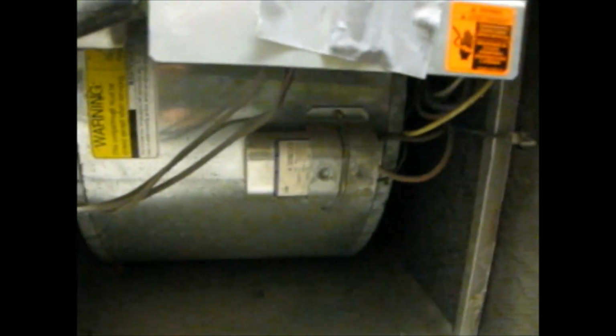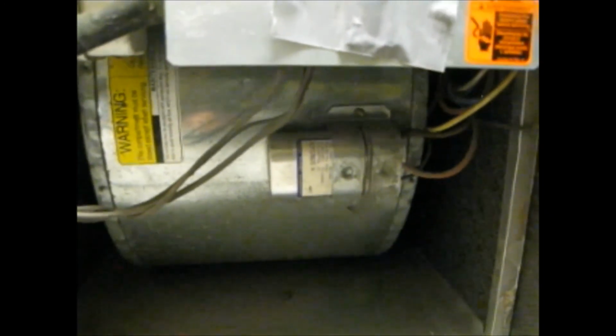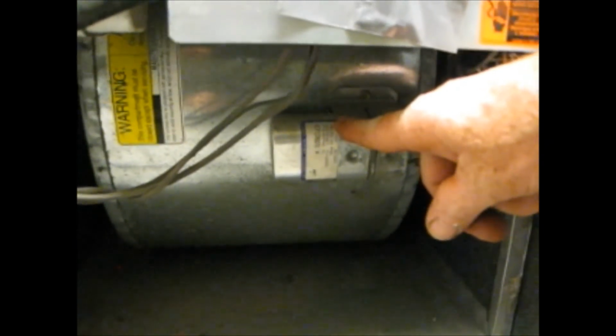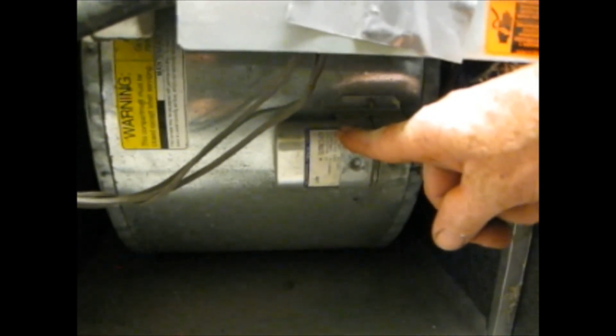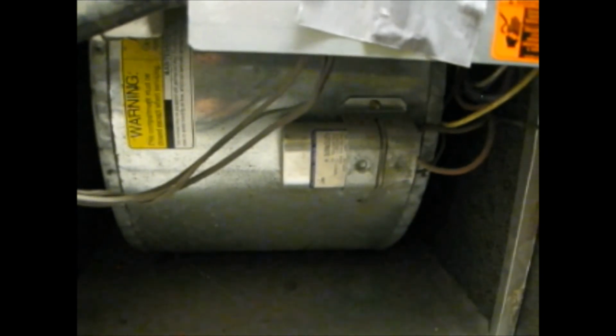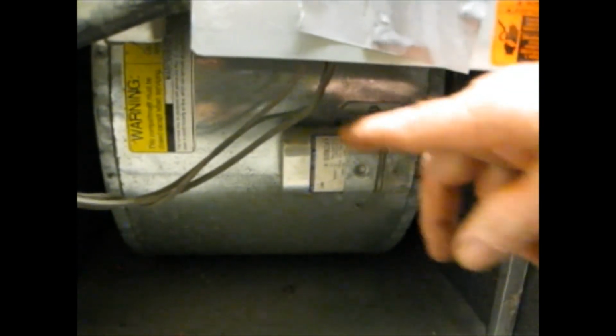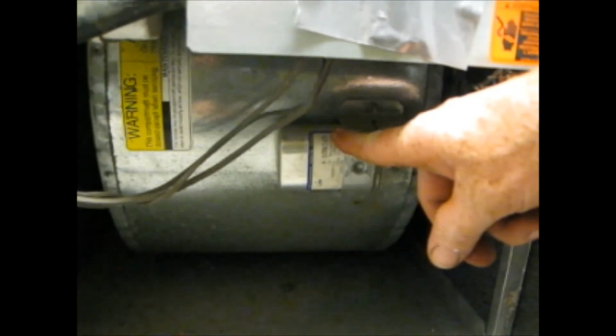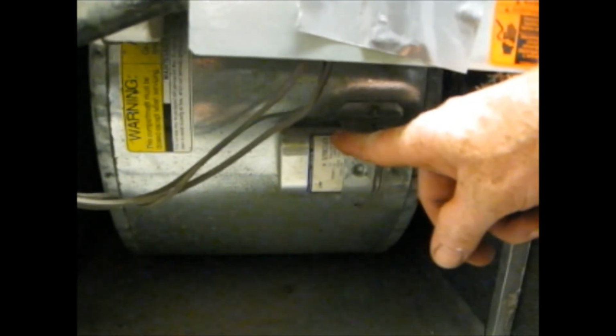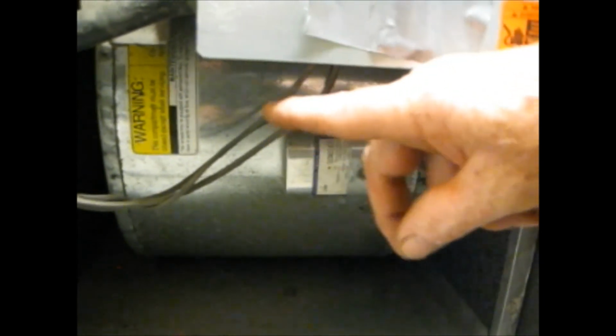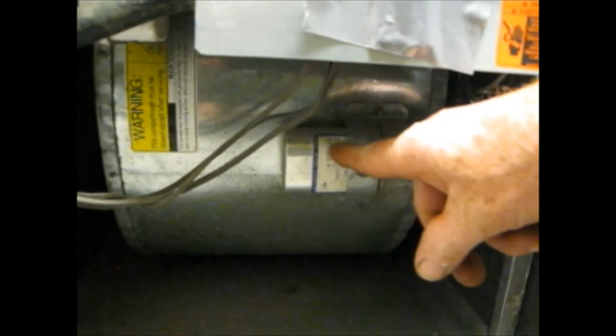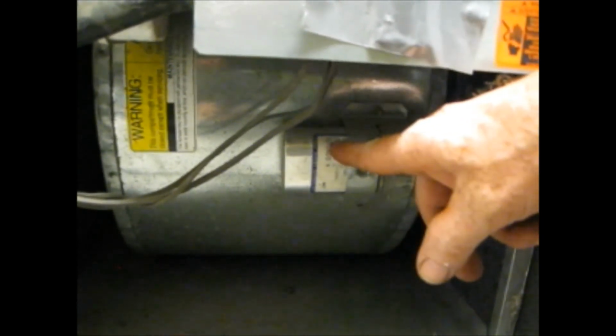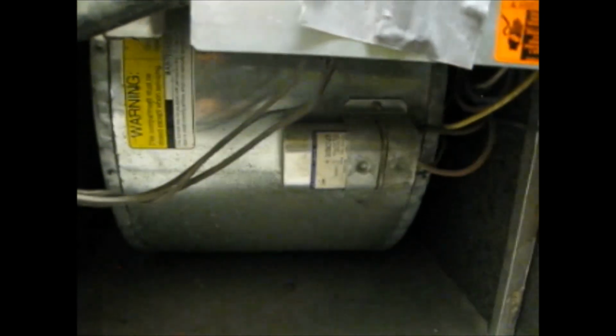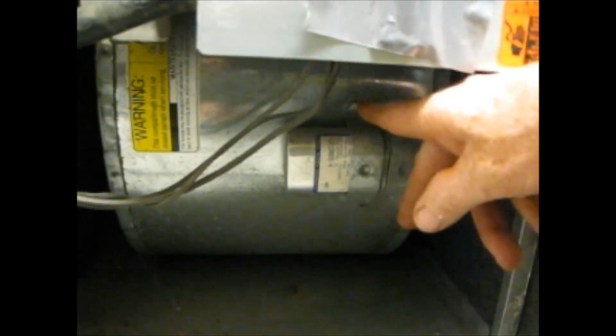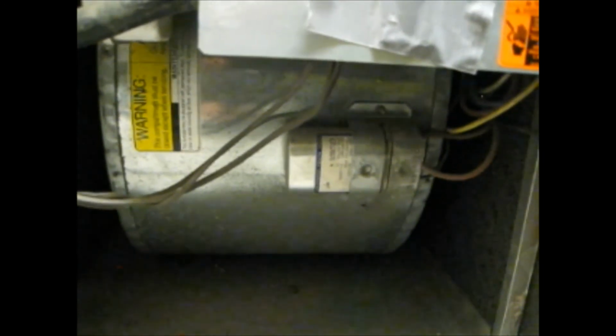Now another thing that could go bad is your big huge blower motor down here on the bottom. This too has a capacitor which can be tested. If you go to turn on your furnace and nothing happens at all, like we said, it should go through a 90-second or so purge cycle. If that's not happening, either your motor could be bad or this capacitor could be bad. So test your capacitor and then test for power going to your motor. Removing this is a little bit more complicated. You might want to call a technician.